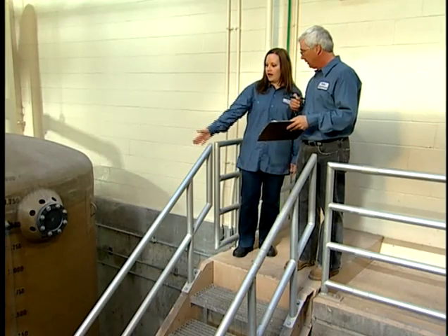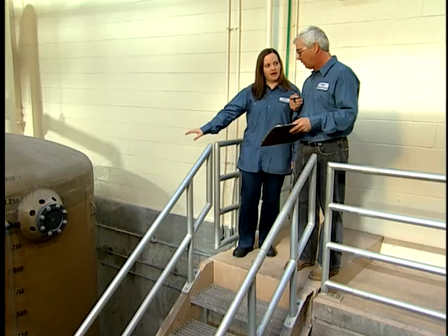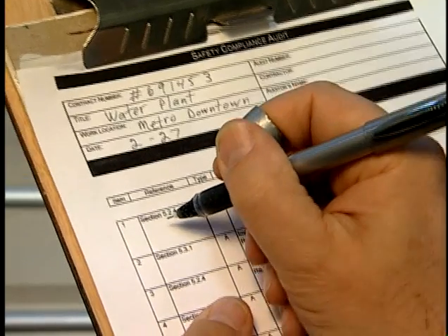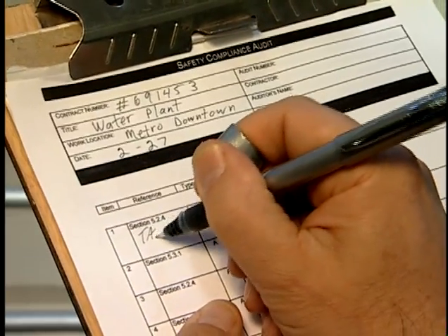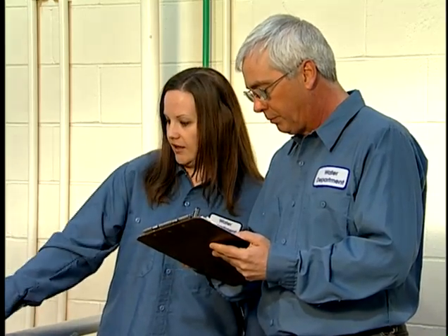The compliance audit must be conducted by at least one person knowledgeable in the process, and a report of the findings of the audit must be developed and documented, noting deficiencies that have been corrected. The 2 most recent compliance audit reports must be kept on file.